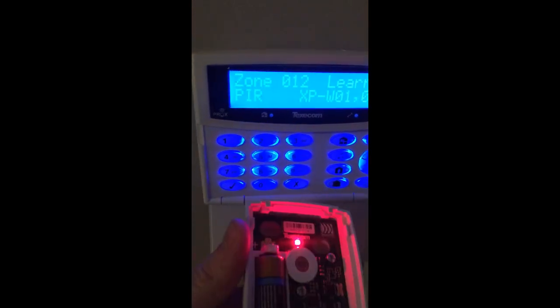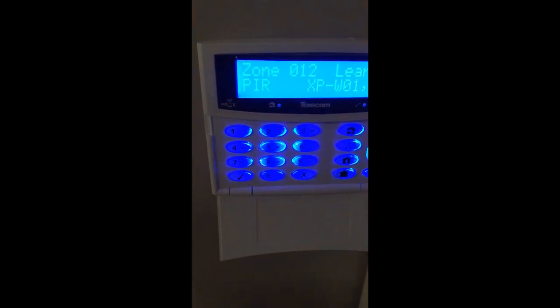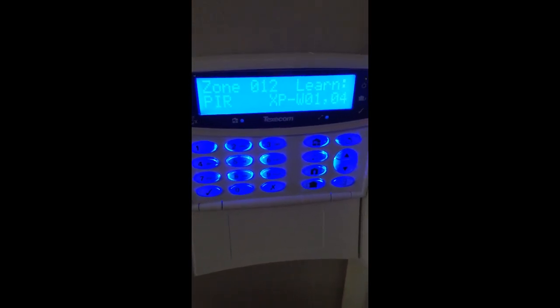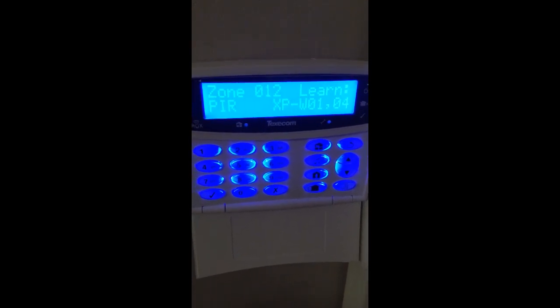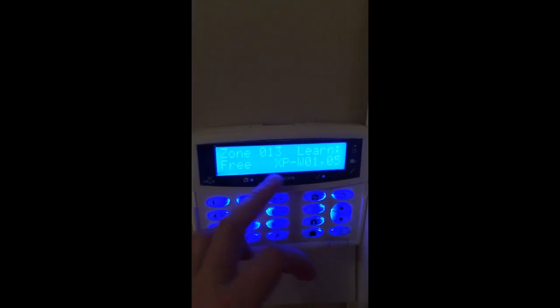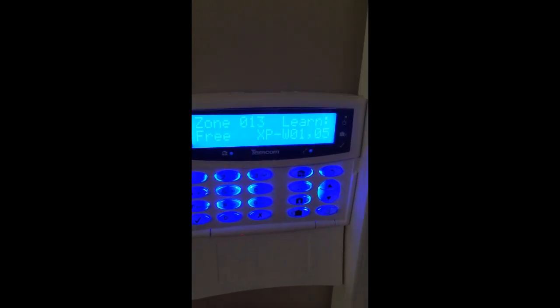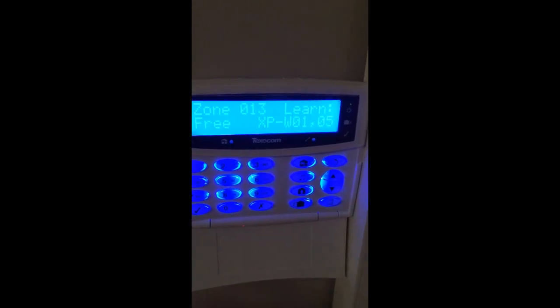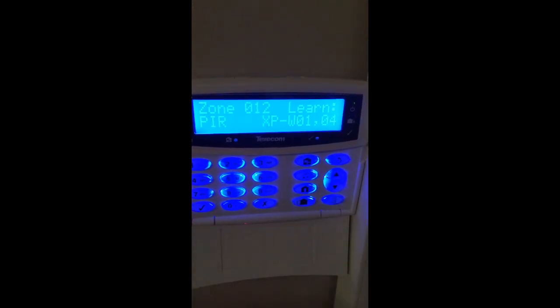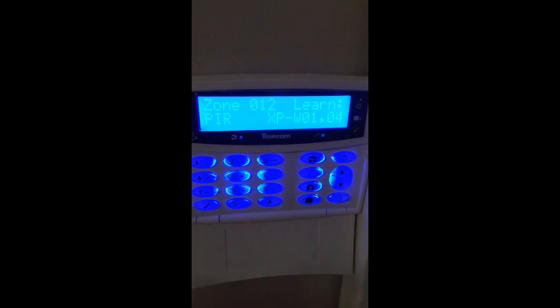That PIR is now in the system. I'll then site it and put it inside the corner of the lounge or the dining room, put the lid on, and as I said, wait 20 minutes before finishing on site. If you have other zones to add, you can press down to go to your next available zone, learn that one, and then site it in its location. Just make sure you write a note as to what zone corresponds to what location so you can complete your zone list. Once you've finished all of them, allow 20 minutes at the end so that it will settle down and establish its Ricochet mesh.